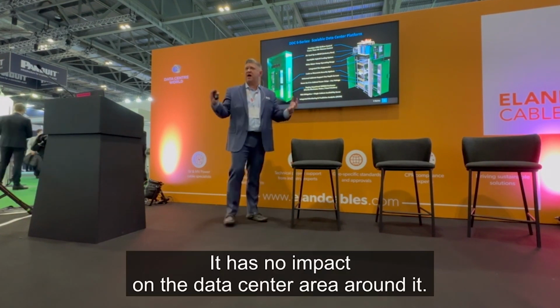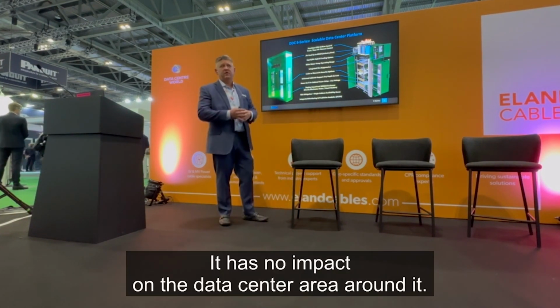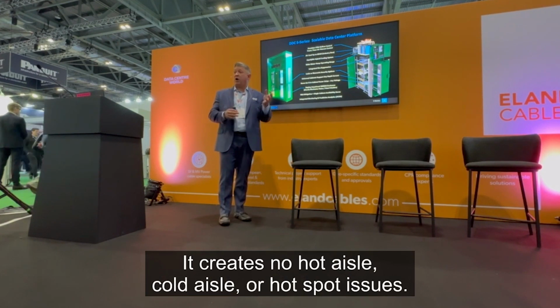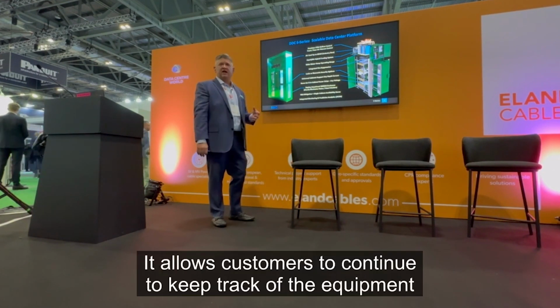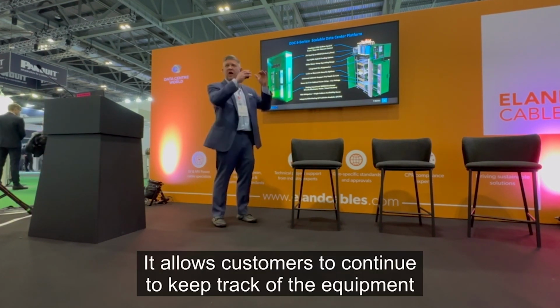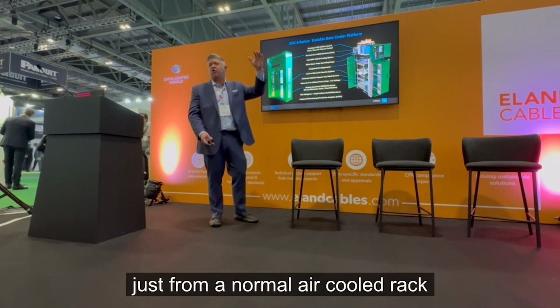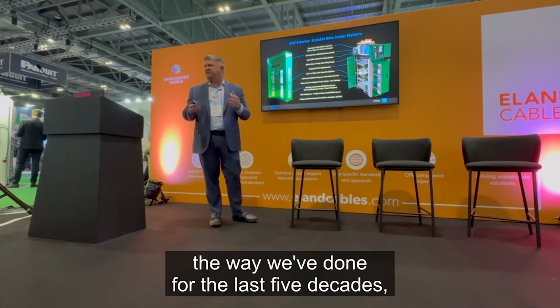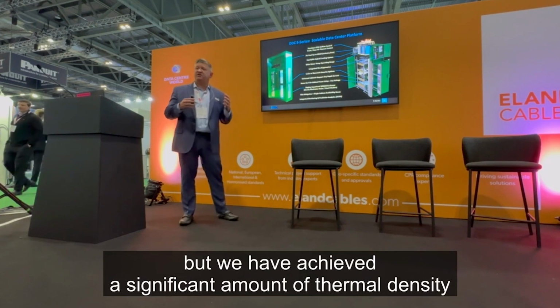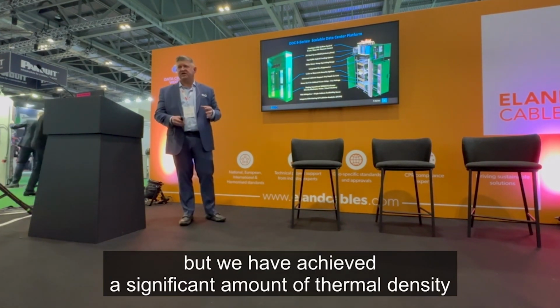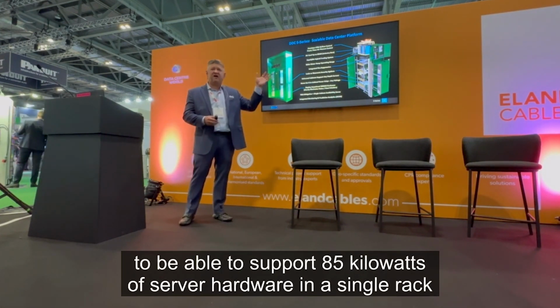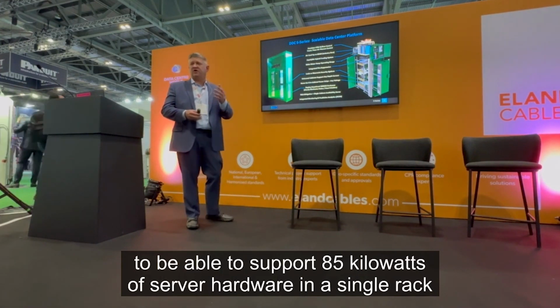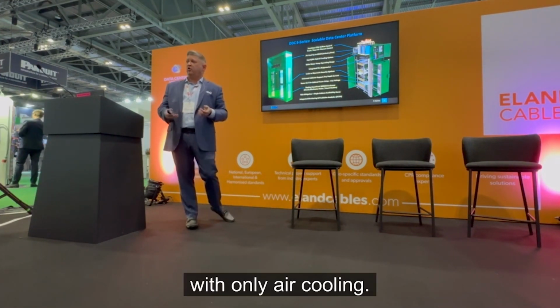It has no impact on the data center area around it. It creates no hot aisle, cold aisle, or hotspot issues. And it allows customers to continue racking equipment in a normal air-cooled rack, the way we've done for the last 5 decades. But we've achieved a significant amount of thermal density, able to support 85 kilowatts of server hardware in a single rack with only air cooling.